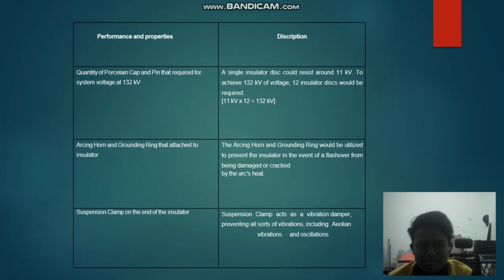So for the performance and properties, this is the quantity of porcelain cap and pin required for a system voltage of 132 kV. Our project uses 11 kV per disc, and the total number of discs we use is 12. The arcing horn and grounding ring attached to the insulator will be utilized to prevent the insulator from being damaged or cracked by the arc heat in the event of flashover. The suspension clamp acts as a vibration damper, preventing all sorts of vibration, including oscillation.